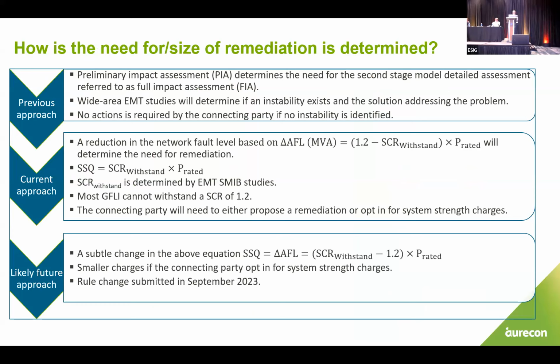Moving to the current approach, that's unfortunately gone. Instead we have this formula, a reduction in the fault level available in the power system. What it tells you is that if the SCR with the withstand capability of the generating system, determined by SMIB EMT studies, is 1.2 or below, that number will be positive, and therefore no remediation is required.